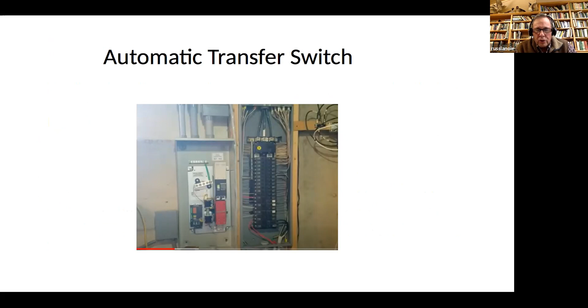They need to be exercised. Even though propane burns clean, one of the manufacturers, Onan, does check the hours on a generator set, and if too few hours, it could void the warranty. They want an average of 24 hours a year to ensure warranty service. So they have to be exercised. I think my friend Wayne told me about 10 to 20 minutes once a week, like you would any generator.